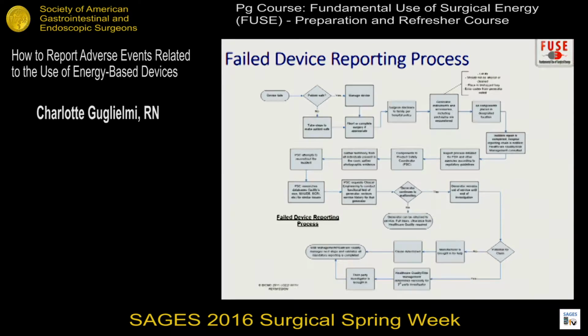Years ago, I helped debrief a situation where we were working with Boston Fire because somebody had a laser burn a hole in the floor and didn't pull the fire alarm. Well, that was a violation of what, in Massachusetts, we have to do when we have a fire in a hospital. So even those kinds of things, you have to pull an alarm, even if the fire marshal is down at the door when they come in and you say, it was not, we took care of it, and then they deal with it. All OR fires have to be reported. In this state, I don't know about other states, but I can only speak to this state.